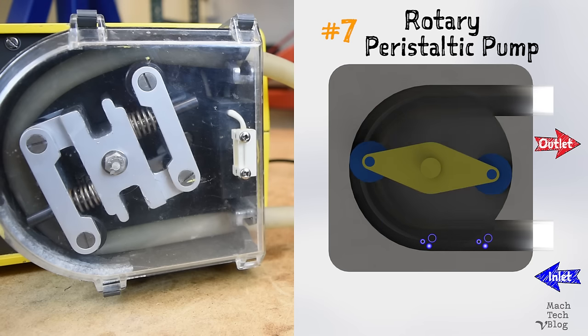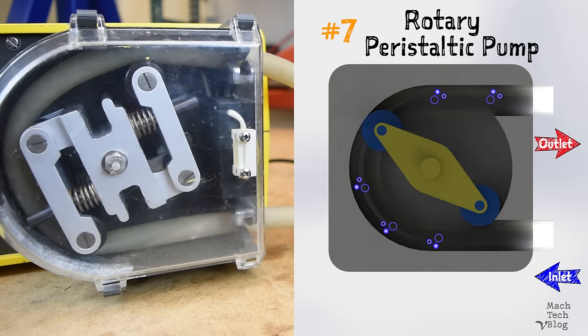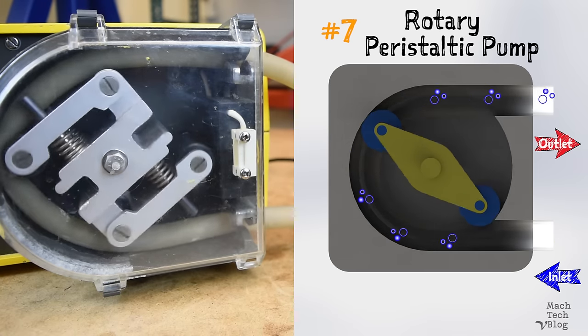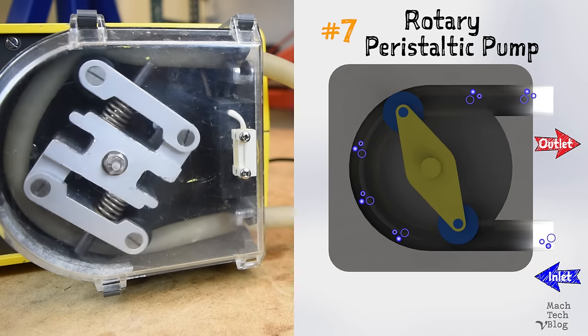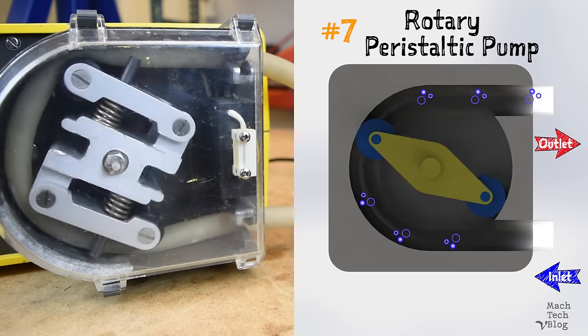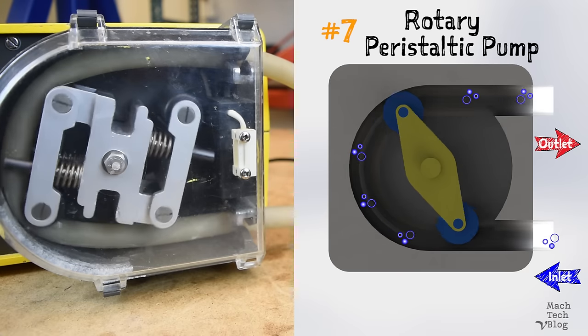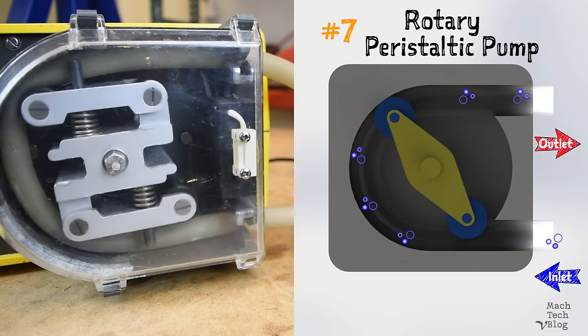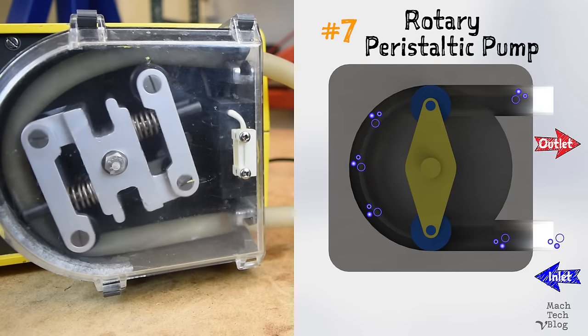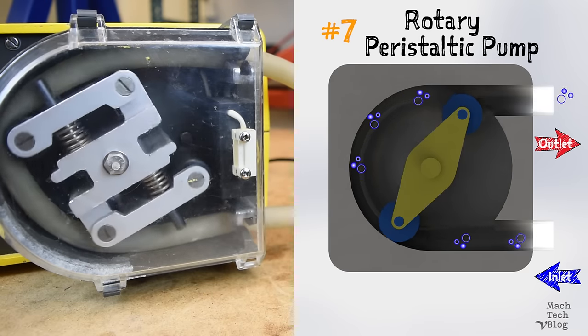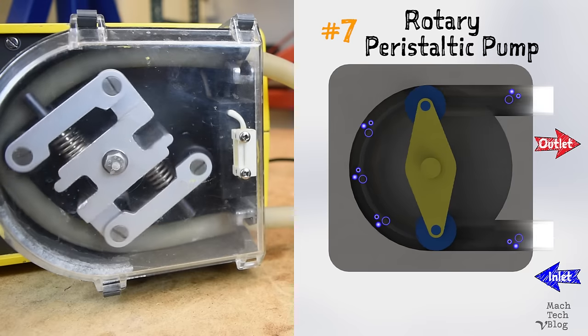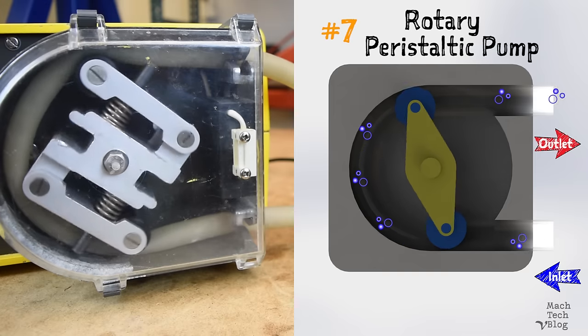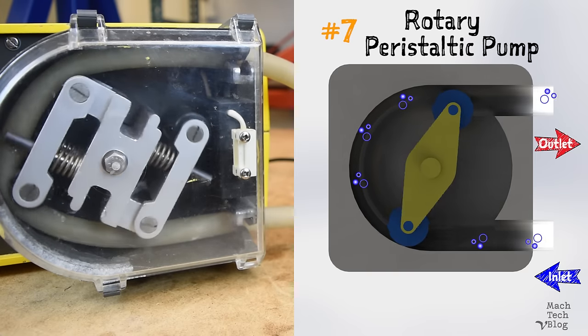Pump number seven is the peristaltic pump. Peristaltic pumps contain fluid within a flexible hose. The hose is pinched between the rollers and the inside wall of the housing. As the rollers revolve around a center axis, they squeeze the fluid like a tube of toothpaste and move it through the housing to the discharge outlet. As with diaphragm pumps, peristaltic pumps do not require a seal, because the fluid is completely contained inside the hose. They really excel at pumping high viscosity fluids with very large solids — I've even seen them pump whole cherries without significantly damaging them.